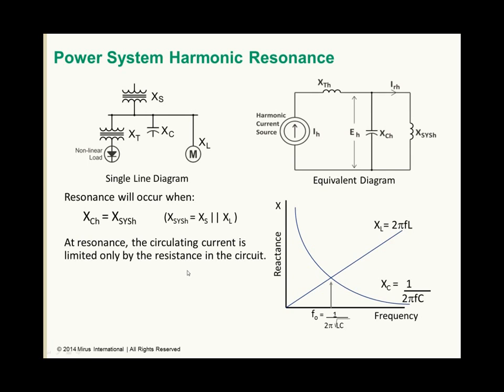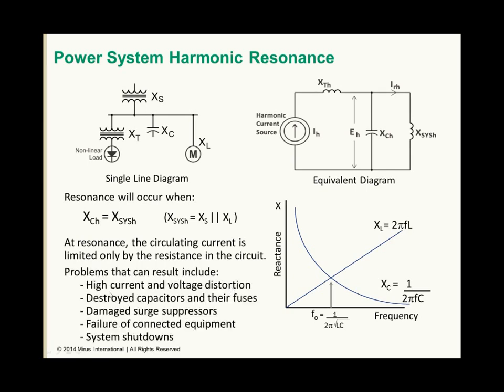but we'll end up with very high current and voltage distortion levels, which can result in destroyed capacitors and fuses protecting those capacitors, and can damage surge suppressors on the power system, be it at the transformers or at sensitive equipment. If the voltage distortion is extremely high, it can result in failure of connected equipment, and in extreme cases can result in power system shutdowns.